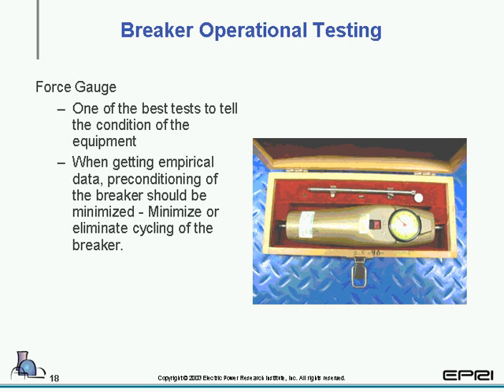One of the tests that we highly recommend for incoming and outgoing as a must-do and as a good indicator of the piece of equipment is a force gauge. Very early on in breaker designs, in the early 40s, 50s, 60s, many force gauge tests were done on the springs, and now in today's breakers they are not truly done as much. There are more force gauges done in the operating mechanism.